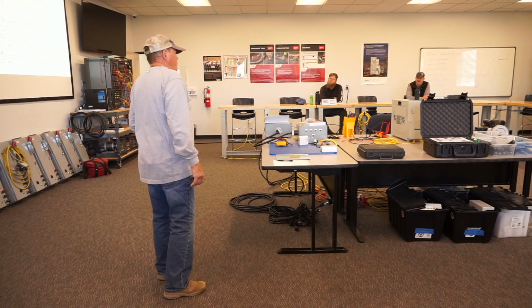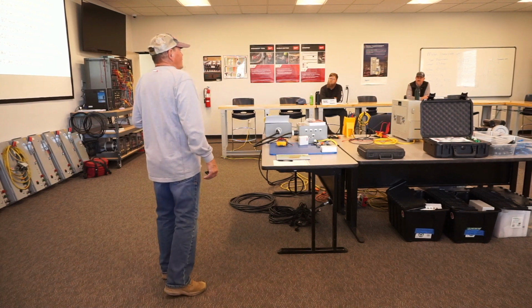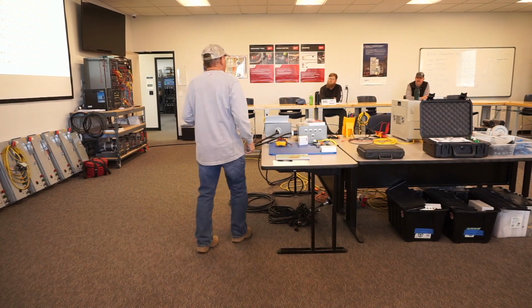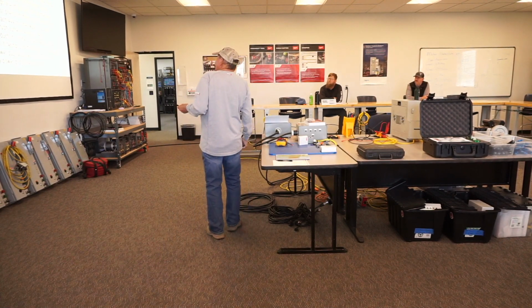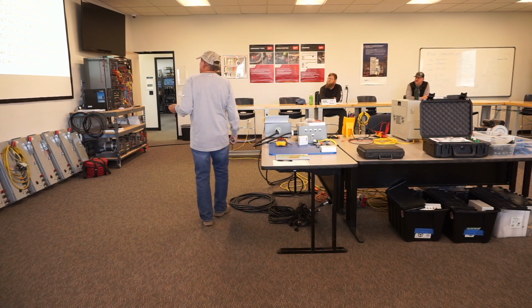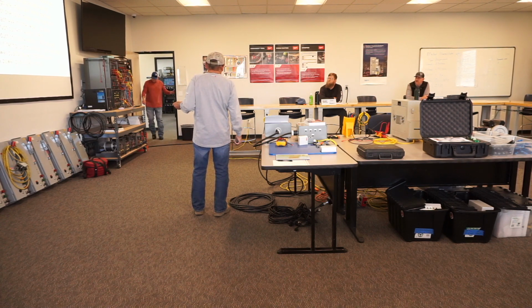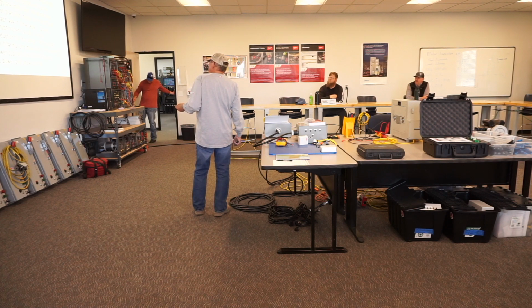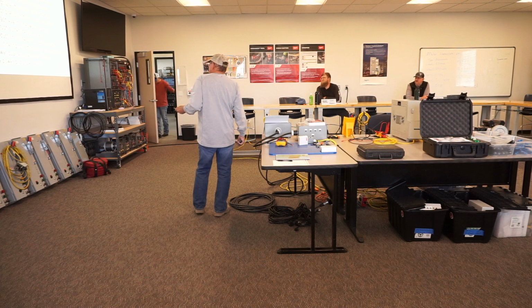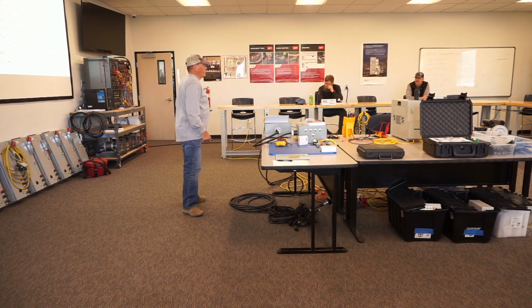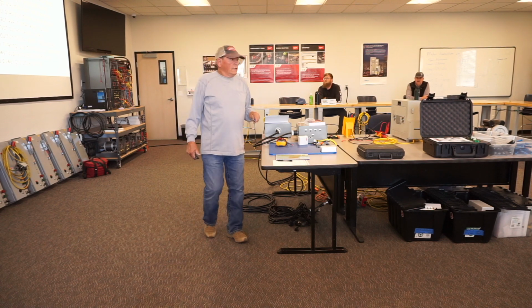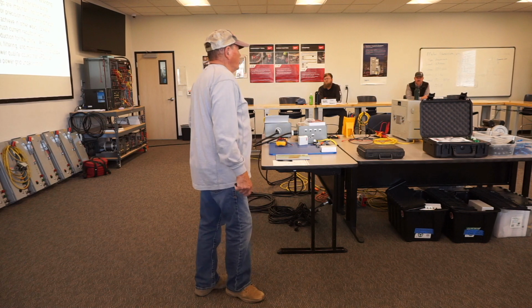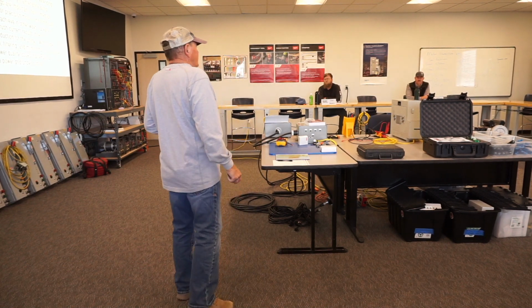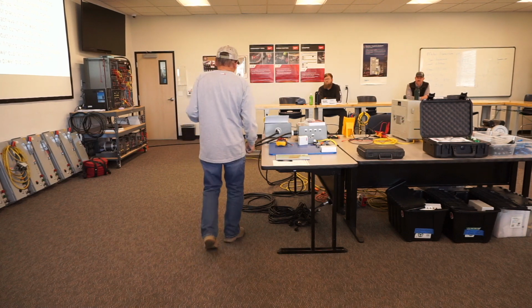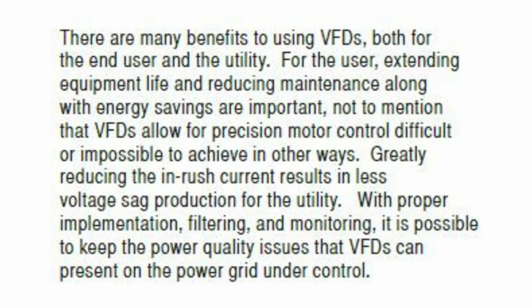Dips. Voltage dips probably in the 60% range when equipment's starting up out there. So, and extends equipment life and reducing maintenance costs. Well, that's kind of a catchphrase, but that's only if it's properly implemented with filtering and you've addressed power quality issues. Without those items addressed, maintenance for VFD motors can be pretty high, real high. And we'll have those answered here before this session ends.